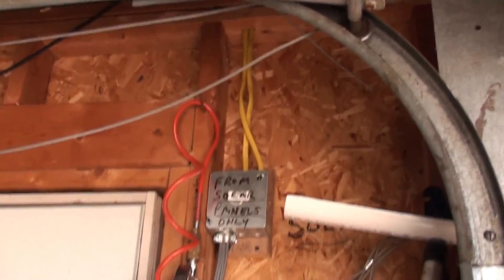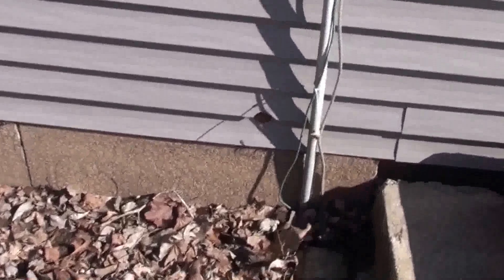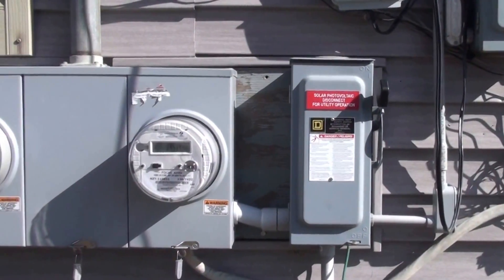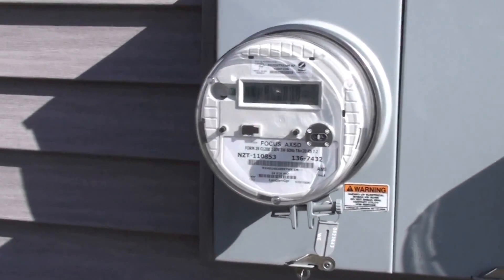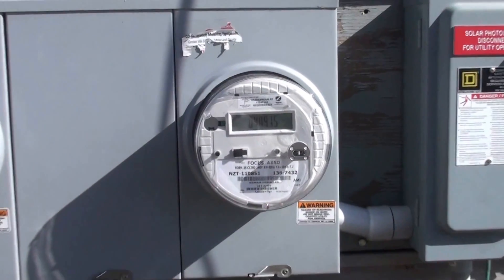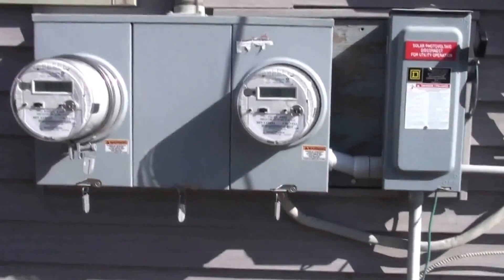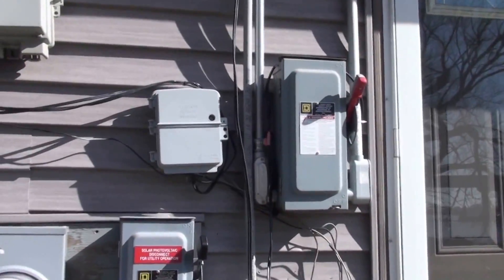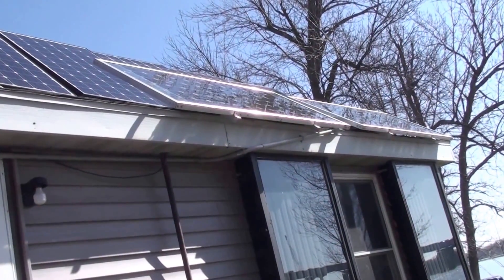These two yellow wires are coming from the solar panels above. They go into number 10 wire and that goes down into the ground and comes over here. This is the way the power company wants it — you wouldn't have to do it this way except that I'm selling back my excess to the power company. It comes over here, goes into this disconnect, and I've got two meters here: this one shows the solar power being generated and this one shows what I'm using in the house. At the end of the monthly billing they subtract what I use from what I made. This other disconnect here is just for these two panels that feed a battery bank I have in the house so that if the power goes off — that's a separate system.